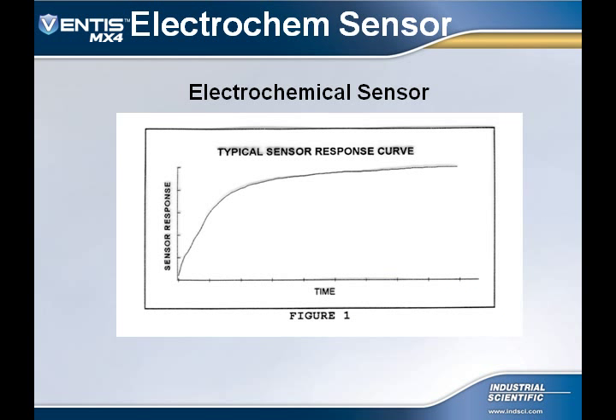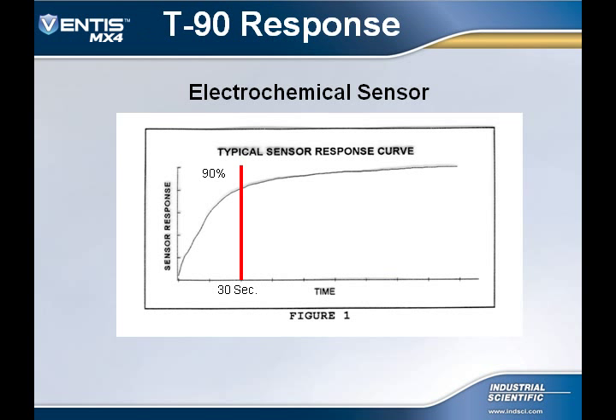This screen shows what I call the electrochemical sensor response curve. What this screen is showing is that it typically takes 30 seconds to respond to 90% of the gas that is in the atmosphere you are testing. To respond to 100% of gas in the atmosphere you are testing, it typically takes 2 minutes.